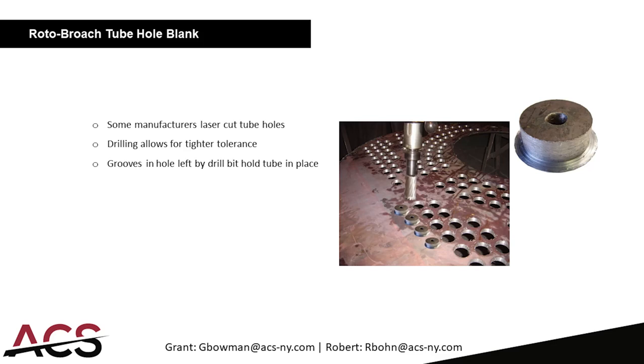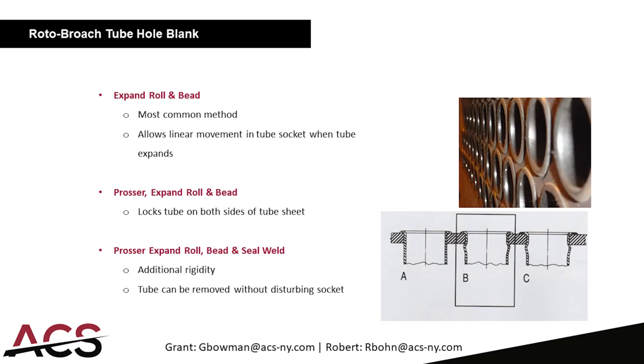Here we have a picture of tubes being rolled and expanded. Option A is the most basic — expanded roll and bead. Option B is the Prosser expand, roll, and bead, which locks the tube on both sides of the tube sheet. Finally, the third option is the Prosser expand, roll, bead, and seal weld for additional rigidity. One application where you'd weld the tubes on both sides is glycol systems, because glycol is a very thin liquid and can find its way through seams between the tube and tube sheet, so welding keeps it from leaking.